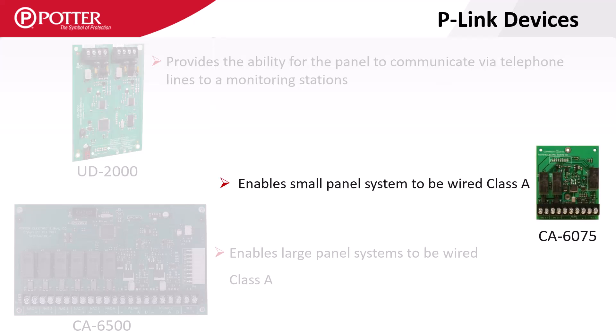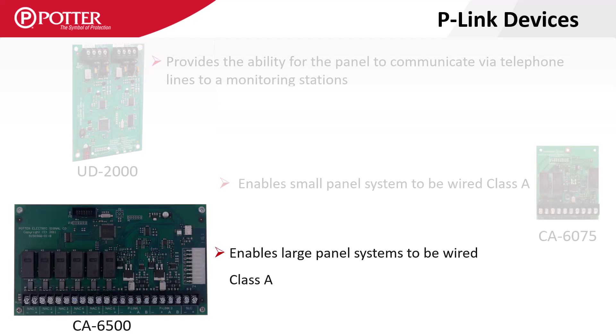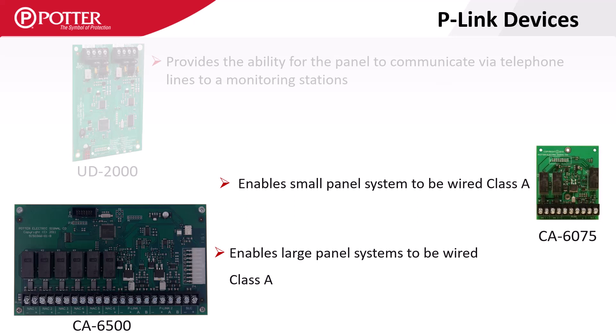There are two different Class-A cards: the CA-6075 for the small format panels and the CA-6500 for the large format panels. Both cards provide the Class-A return terminals for NAC circuits, P-Link circuits, and SLC, all of which are independently configurable. The I-O circuits can only be Class-B.